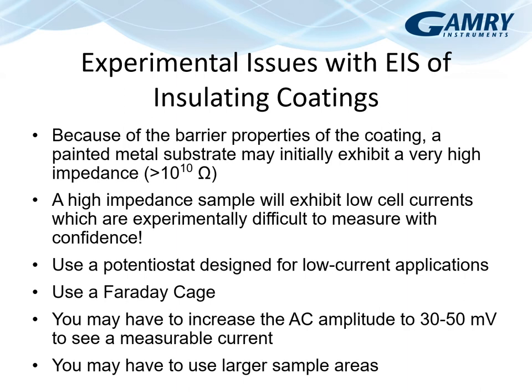Even with a good low-current potentiostat like the Reference 600+ and a Faraday cage, current signals may be too small — you may run up against the capacitive limit or current measurement limitations. One option is to increase the AC amplitude: normally 10 mV is the practical limit for electrochemistry to maintain a linear signal, and 15 mV is probably the maximum worth attempting. Coatings are a special case — with an intact barrier coating there is no electrochemistry happening, so a higher AC amplitude gives more current signal without inducing nonlinear harmonics.